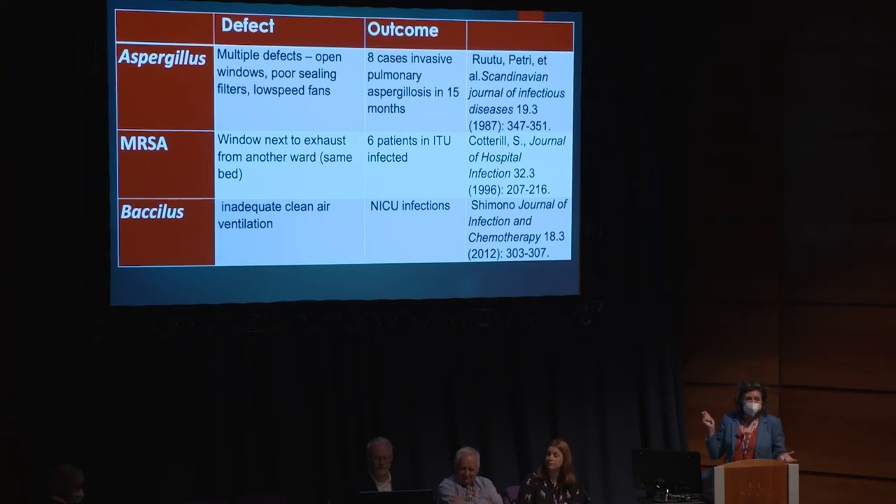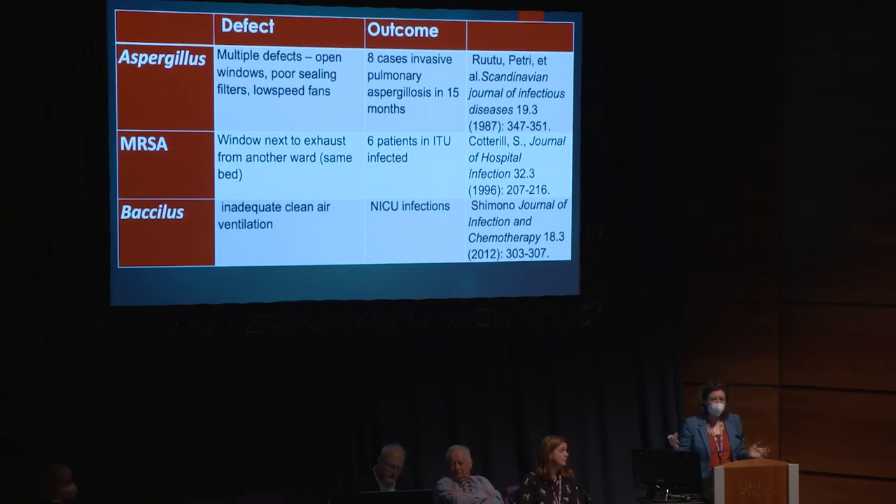Please do look up the references - they document meticulous research on what has gone wrong. Eight cases of pulmonary aspergillosis because windows are open with poor sealing filters, slow-speed fans. An MRSA outbreak in an ITU that was always in the same bed - it turned out the exhaust from another ward was coming straight through the window onto that bed. NICU infections with no clean air coming in from anywhere. What you get is months, possibly years of nothing, no problems - then suddenly all the holes in the cheese align and boom. That is the story of infection control.